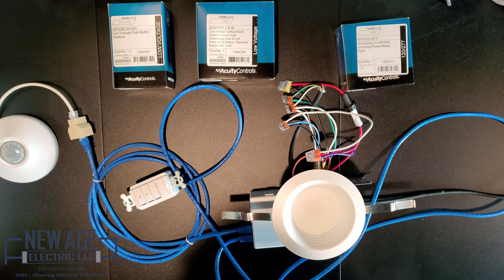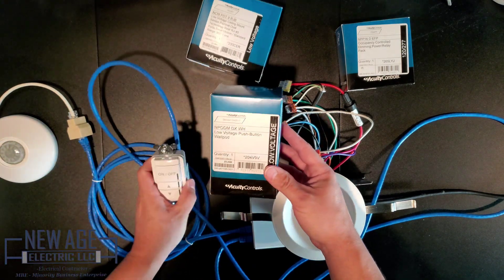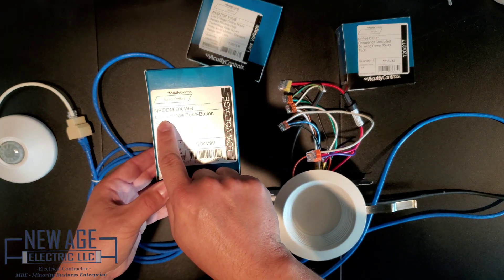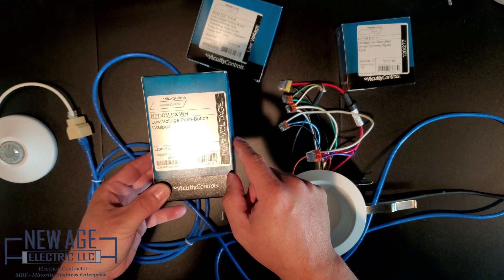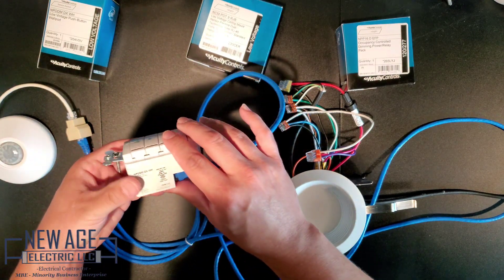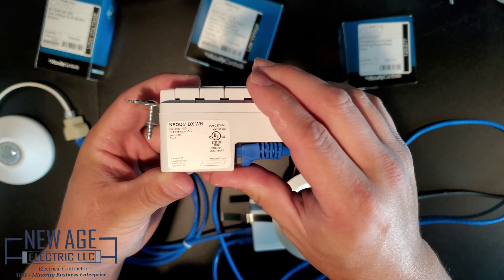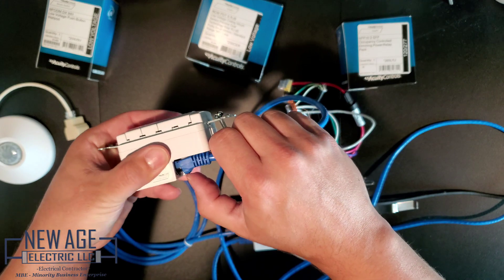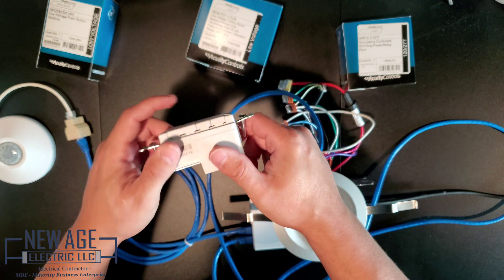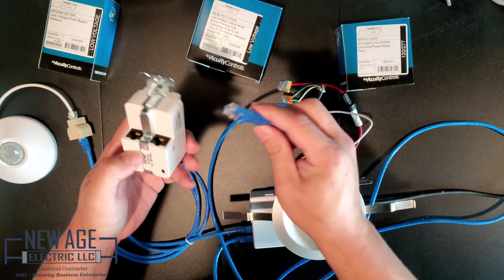We have a couple of products in front of us. We have the low voltage push button wall pod — this has an on and off feature with raise and lower for lighting. This is the N-P-O-D-M-D-X-W-H, which is the white low voltage push button wall pod. These actually operate at 24 volts DC. Behind this switch itself — let me unplug this — this is a Cat6 cable. You can notice that there are no line voltage screws, nothing in here. It's basically an in and out with a Cat5e RJ45 jack inside. So I'm going to plug this back in.